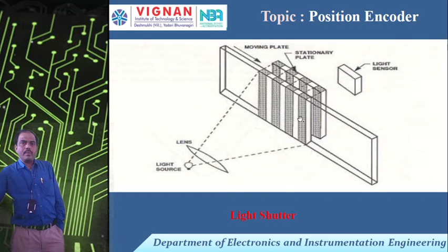As we know, the transparent and opaque parts are equidistant. For example, if there are 10 opaque and transparent paths over 10 centimeters, and it produces 20 pulses, then you can say that 20 centimeters of displacement has taken place. That means the number of pulses reflects the amount of displacement, depending upon the number of opaque and transparent paths, which are already fixed. So the number of pulses can provide the displacement or position. Generally this is the principle of linear and rotary incremental position encoders.